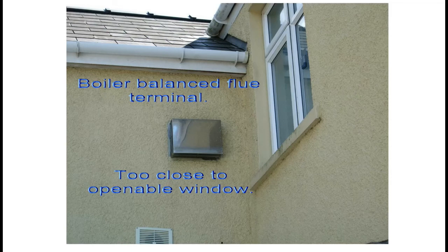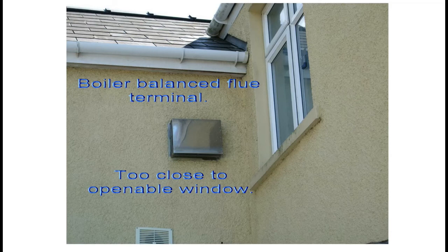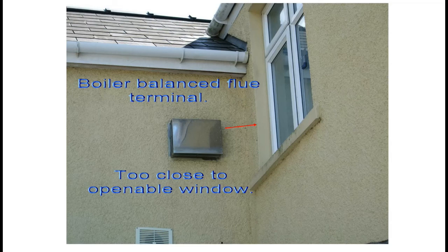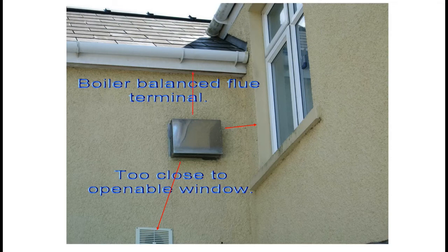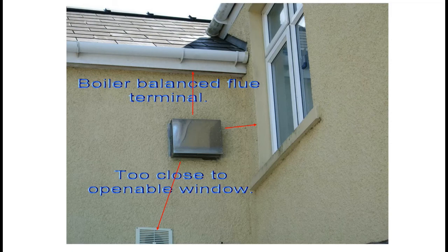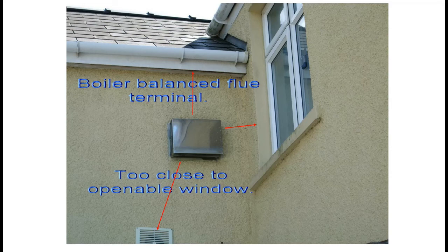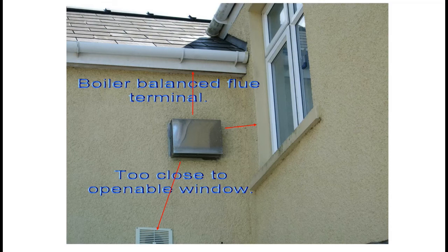And where it's positioned is quite complex from a location point of view because you've got to worry about A, its distance from the window, B, its distance from that ventilation hole, and C, its distance from the soffit and plastic gutter. All of these things have to be taken into consideration. If you look at your chart, you'll be able to see how close a balanced flue terminal is allowed to be to a window.